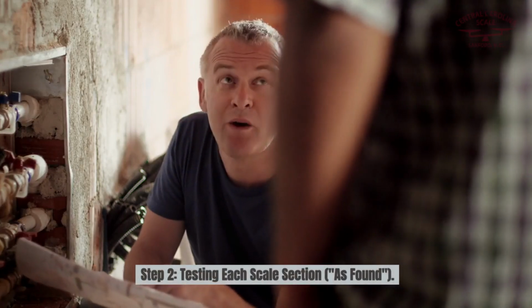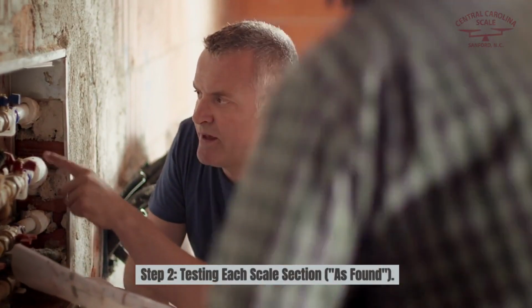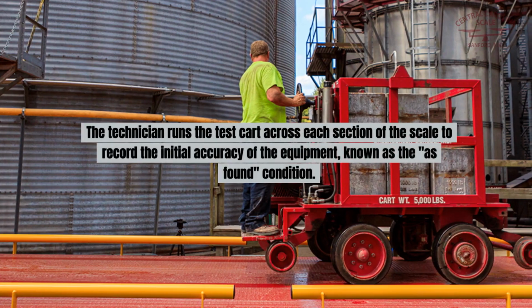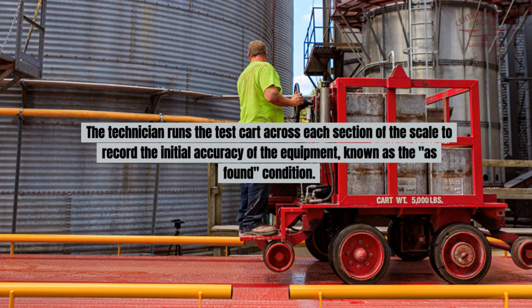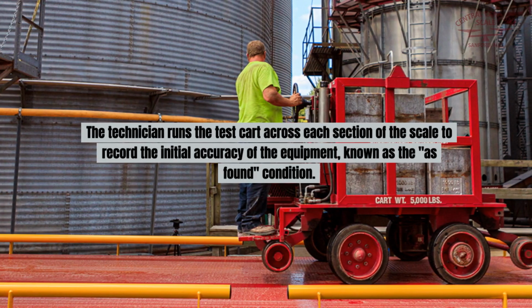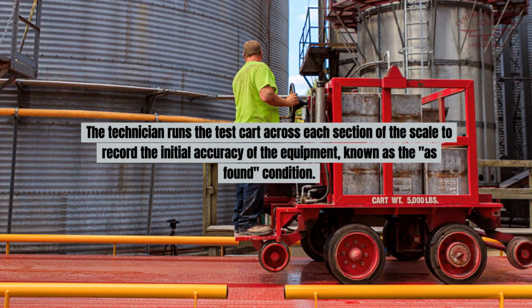Step 2. Testing each scale section, as found. The technician runs the test cart across each section of the scale to record the initial accuracy of the equipment, known as the as-found condition. This provides a snapshot of how the scale is performing before any adjustments are made.